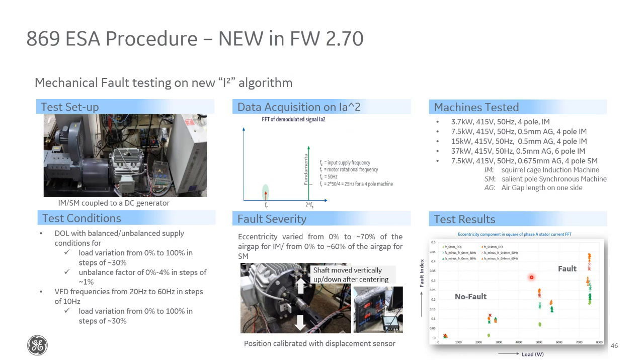You can see on the bottom right here the results of various tests, and you can see there was a clear distinction between what the relay saw when there was no fault present versus when we induced a fault. So from all of our testing, we find the I-squared algorithm that we use is much, much easier of an analysis and much more accurate than just using the standard FFT on the stator current.